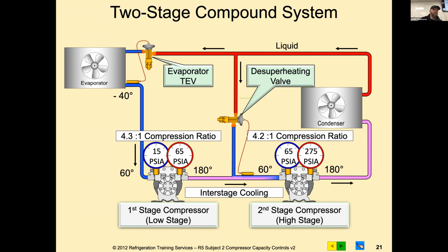So you would be dealing with, like we saw on the last slide on R22, something like an 18 to 1, which would smoke the compressor and the oil. Now, by having two compressors like that with that one evaporator, what that actually does is help to bring down the temperature in that evaporator quicker.